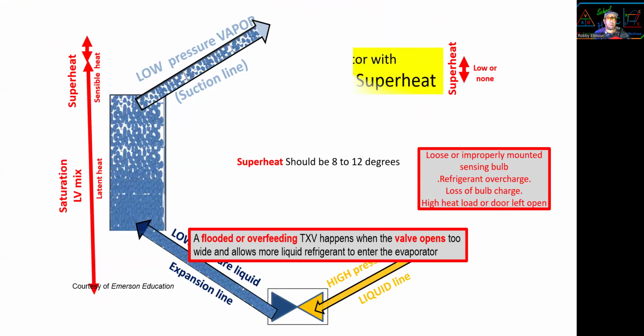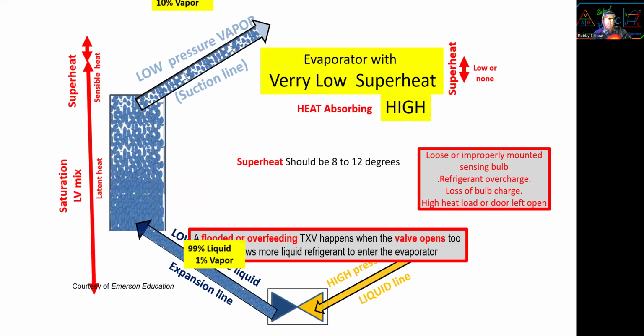Right now, superheat should be 8 to 12. Evaporator with very low superheat: all right, it's flooded. The evaporator is flooded. The TXV valve is open too much. All right, 99% liquid in, and 90%, 10% vapor. We have barely any superheat, right? Heat absorption is high. It is efficient, okay?